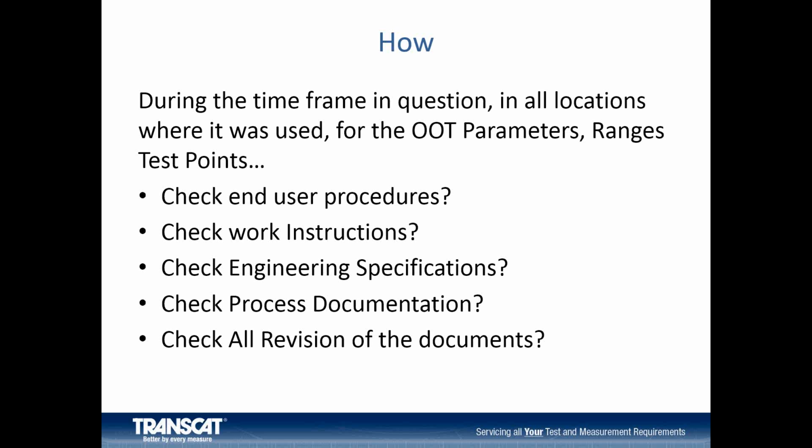During one training session, we identified an issue that there was a revision change in one of our procedures during the time frame in question. So we had to go back and pull the reference procedure for the previous rev to see if the process tolerance had changed. In our case, it hadn't. So it was just a lesson to be learned to look at all the previous revisions of your documentation.